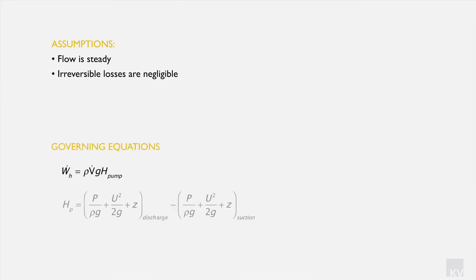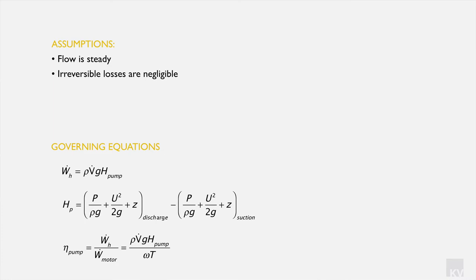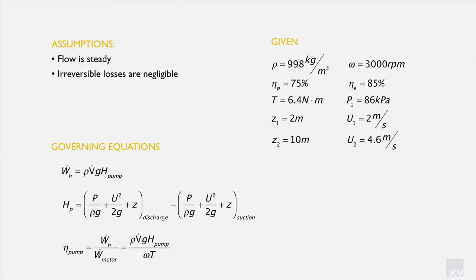The governing equations we're going to use — just three of them. The first is the work required to generate the head: density times volumetric flow rate times gravity times pump head. The pump head is the discharge side minus the suction side, comprising the pressure element, the kinetic element, and the potential element at each side. Finally, pump efficiency equals work required to generate the head divided by the work the motor must do.